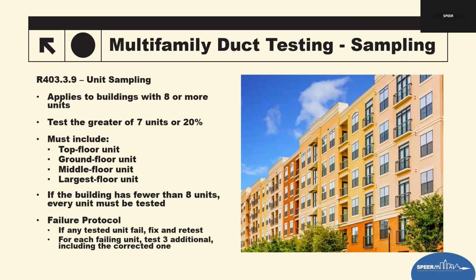Multifamily sampling, we'll walk through this. It's the exact same thing for blower door, mechanical ventilation, and of course duct testing. So instead of testing every unit, code now allows for a sampling strategy or sampling protocol, but only when the building is large enough. The same protocol applies for blower door and mechanical ventilation. For buildings with 8 or more dwelling or sleeping units, we do not have to test every single unit. Instead, we test the greater of 7 units or 20% of units, whichever is higher. The sample group must be representative.